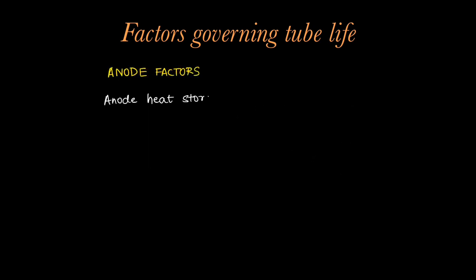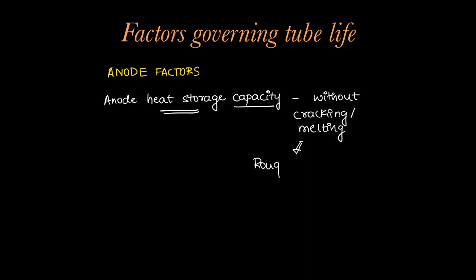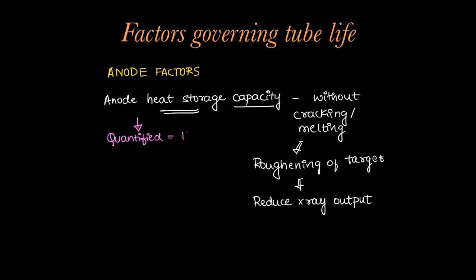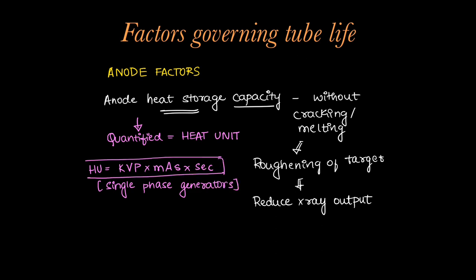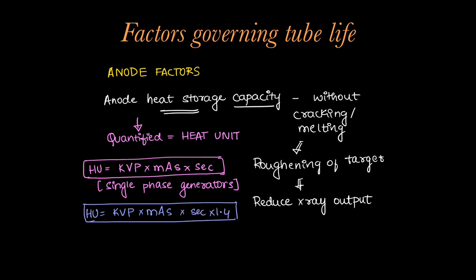Coming to anode factors, each anode has an anode heat storage capacity which is a standard for itself — it is how much heat it is able to bear without cracking or melting. Cracking or melting will cause roughening of the target surface which reduces x-ray output. This heat storage capacity can be quantified in heat units. The heat unit is KVP multiplied by MAS multiplied by seconds for single phase generators. For a three phase generator, the formula is KVP × MAS × seconds × 1.4. Nowadays we use three phase generators, so we use this formula.